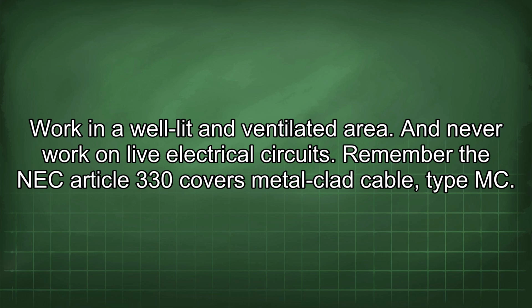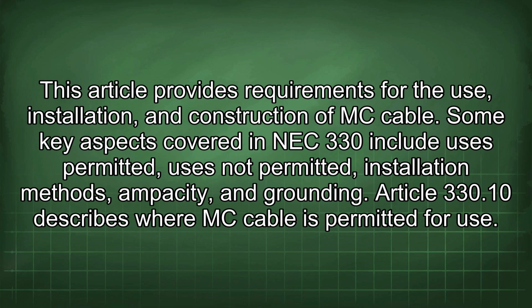Remember, NEC Article 330 covers metal-clad cable type MC. This article provides requirements for the use, installation, and construction of MC cable. Some key aspects covered in NEC 330 include uses permitted, uses not permitted, installation methods, ampacity, and grounding. Article 330.10 describes where MC cable is permitted for use.